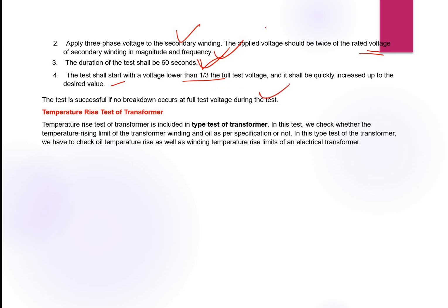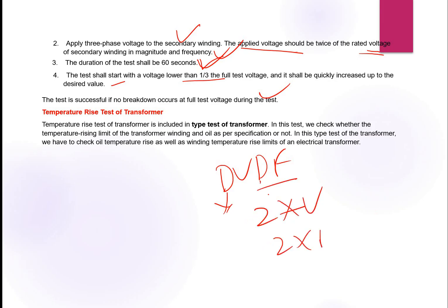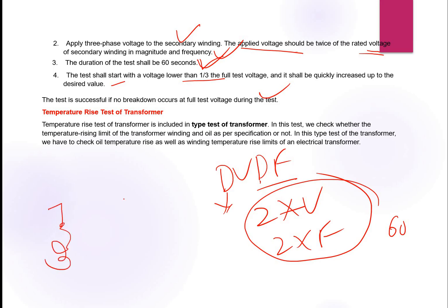One condition is the applied voltage should be twice the rated voltage. Induced voltage means DVDF, double voltage, double frequency, 2 times V and 2 times frequency. In this test, for 60 seconds, this is the transformer, this is the applied voltage on the secondary side, and I keep the LV open.